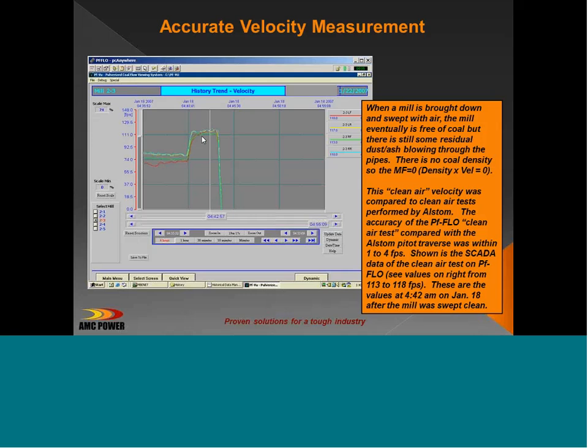Coal particles will always move slower than air. They have to. It's the friction between them that carries them to the burner. How much slower depends on the fineness of the coal, the moisture content, piping runs, and so forth. But this also tells us why manual sampling is not an accurate way to measure flow, because manual sampling tells you to first measure the speed of the air and then extract your coal at that speed. Well, the air speed and the coal speed are very different, so you can't infer one from the other.